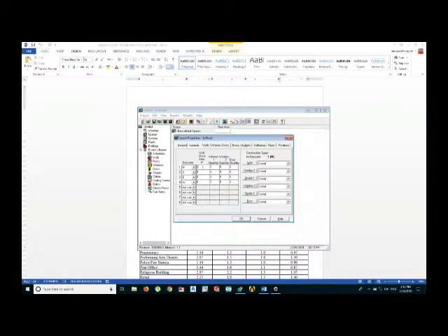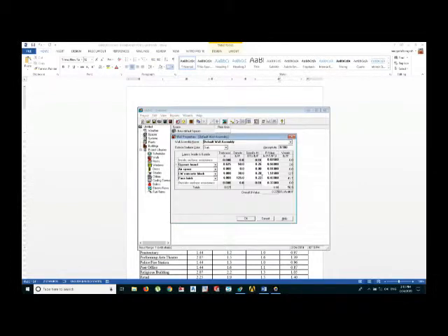And this is the wall gross area. Like my office is 10 by 10 and height is 9, so the wall area will be 10 by 9, which is 90. All walls are the same, so these all will be 90 square feet. You can define also window, if there is a window in your north wall, or maybe there is a window in south wall, 1, 2, 3, how many windows. You can define these doors, how many doors here. And last thing is, you will define the wall assembly, from which material your wall is made up of.